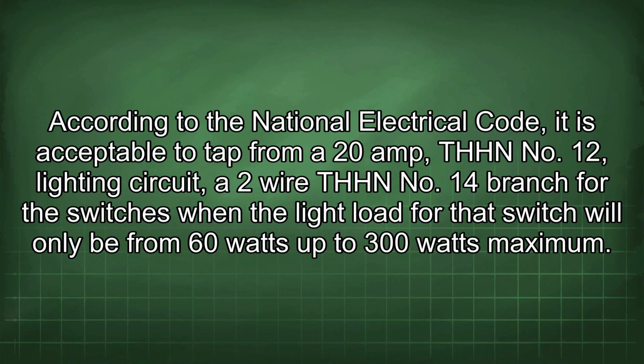According to the National Electrical Code, it is acceptable to tap from a 20 amp THHN 12 lighting circuit a 2-wire THHN 14 branch for the switches when the light load for that switch will only be from 60 watts up to 300 watts maximum.